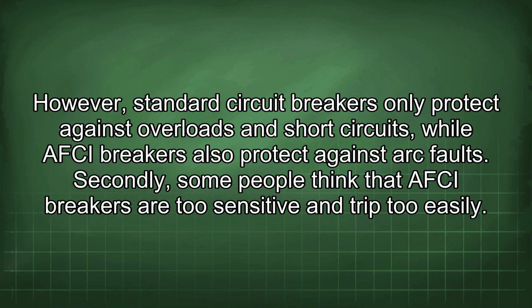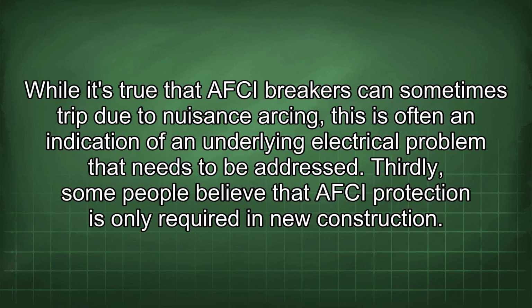However, standard circuit breakers only protect against overloads and short circuits, while AFCI breakers also protect against arc faults. Secondly, some people think that AFCI breakers are too sensitive and trip too easily. While it's true that AFCI breakers can sometimes trip due to nuisance arcing, this is often an indication of an underlying electrical problem that needs to be addressed.